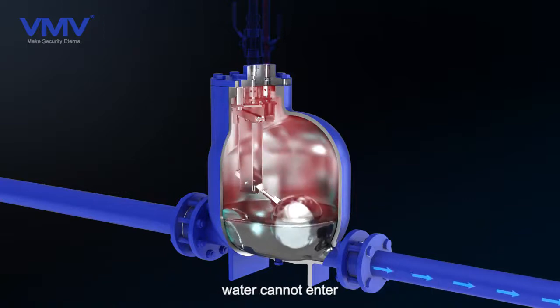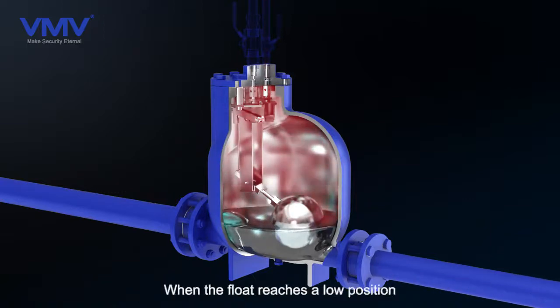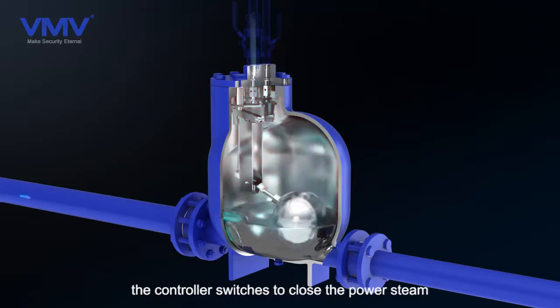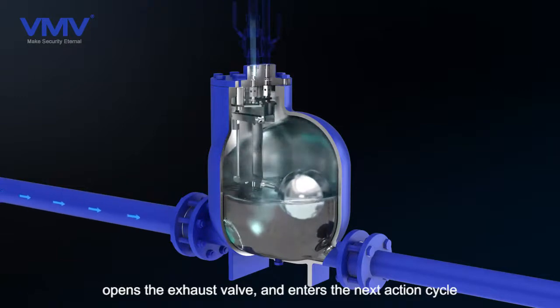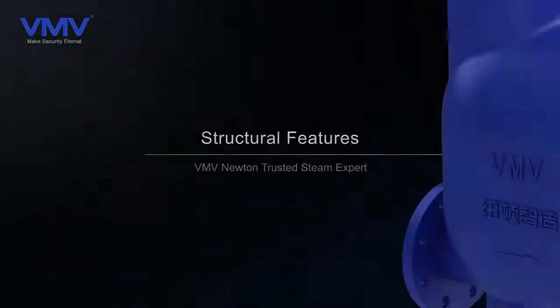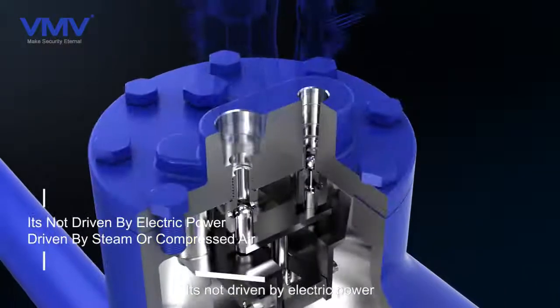Then the inlet check valve closes due to the high pressure inside the valve, and water cannot enter. When the float reaches a low position, the controller switches to close the power steam, opens the exhaust valve, and enters the next action cycle.